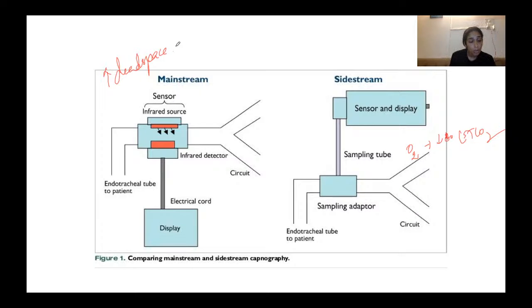So with mainstream carbon dioxide, condensed water secretions or blood on the window of the cuvette can interfere, that we discussed. The sensor may become dislodged. Because of the bulk, if the sensor becomes dislodged from the cuvette, no waveform will be seen at all. Even slightly dislodged, an incorrect reading may be obtained even though the waveform appears. Then the sensor that has to be replaced if damage occurs is really expensive.